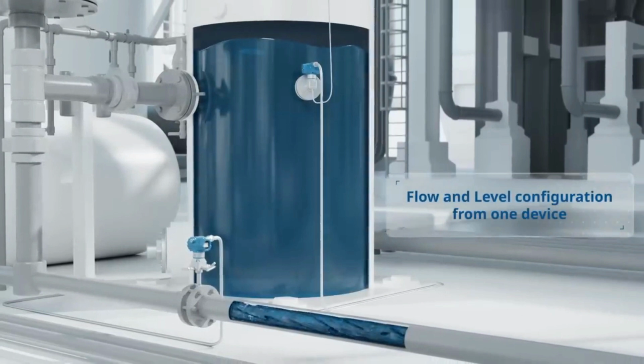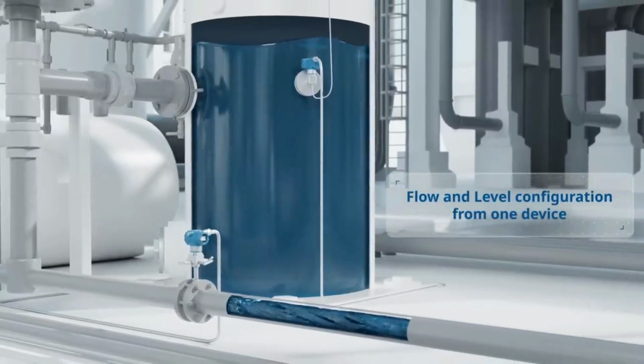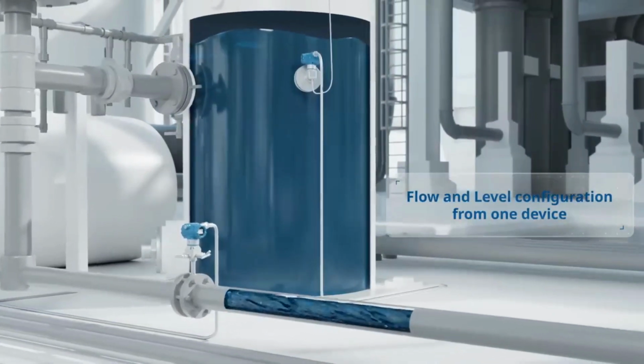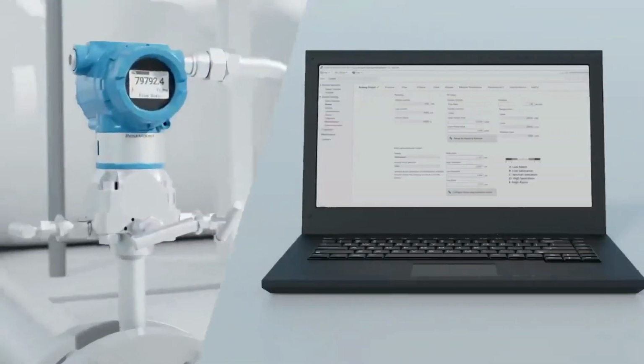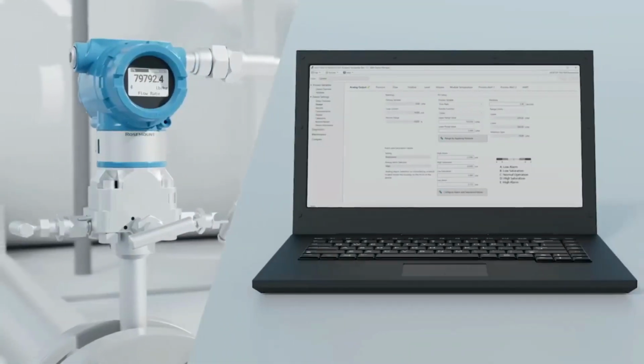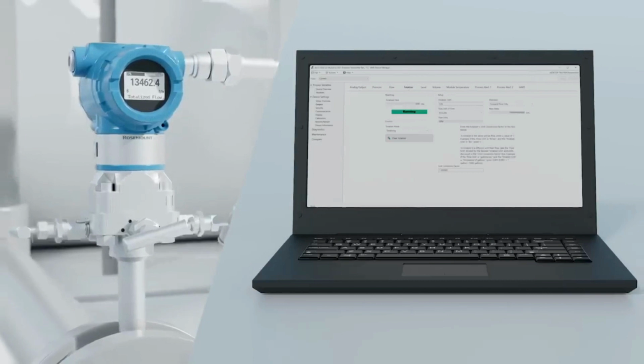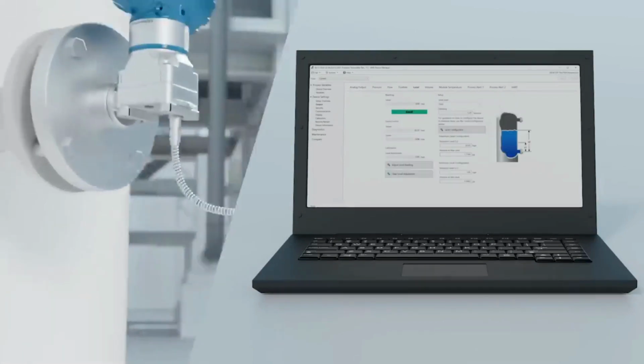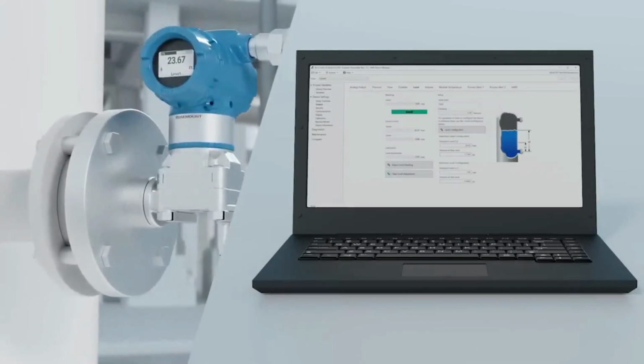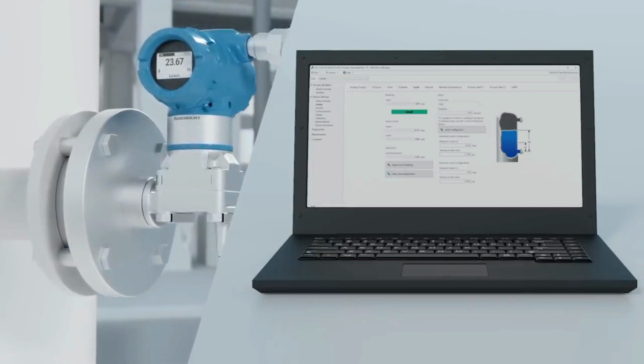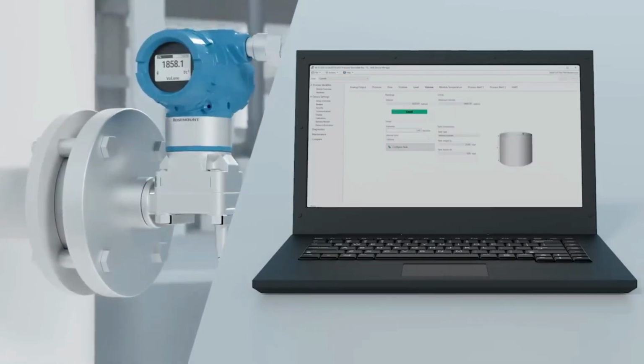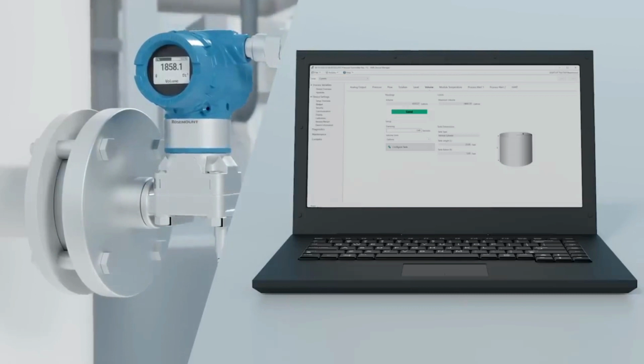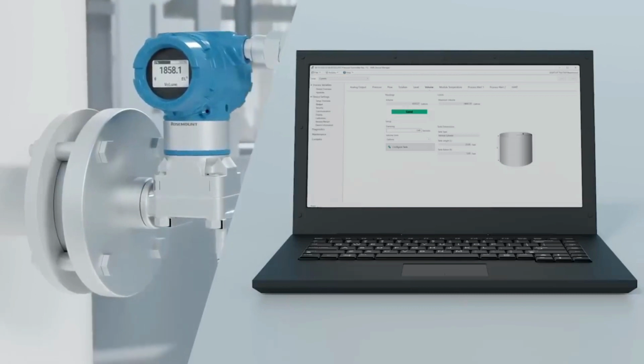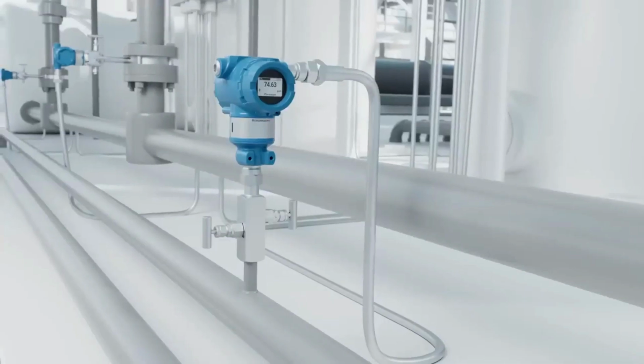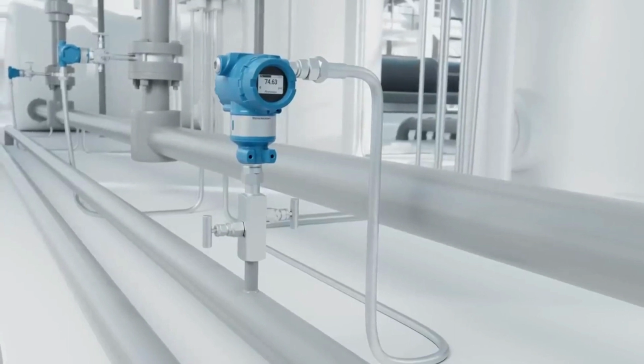Your pressure transmitter now includes capabilities that have historically been limited to flow meters and level devices. You can easily configure the device to measure flow rate as well as track totalized flow. Level measurements have been made simple with a built-in configurator to guide you through setting up level output. Volume measurements are also possible for common tank styles or even customized tanks that require a strapping table. Identify issues with 3051 diagnostics.